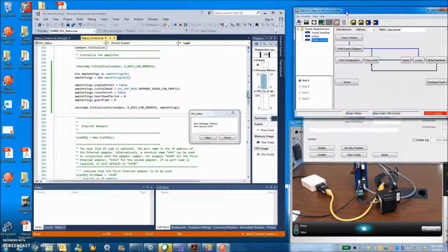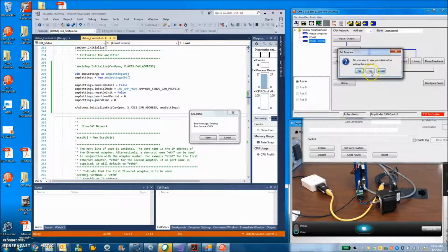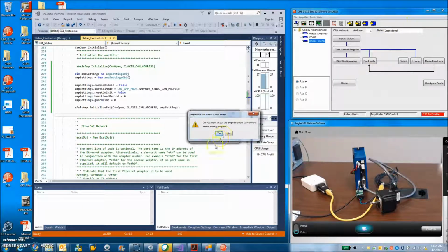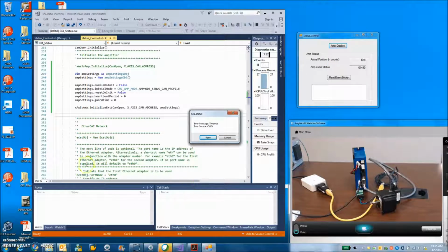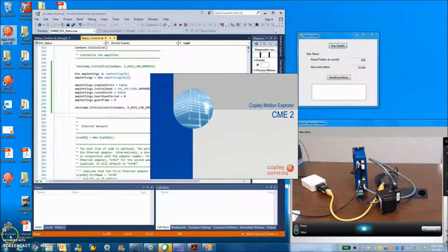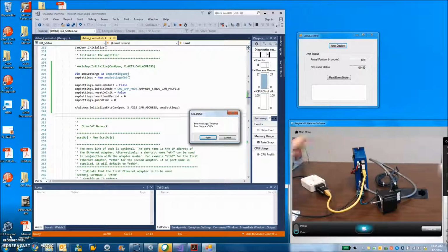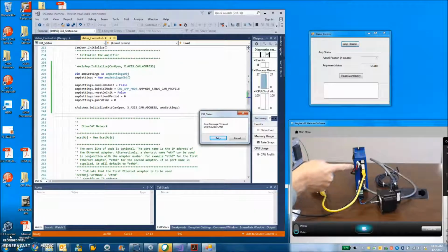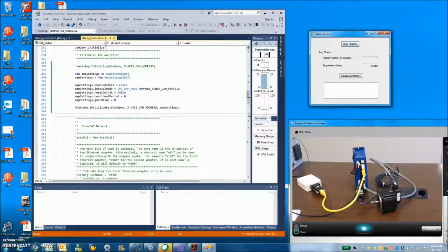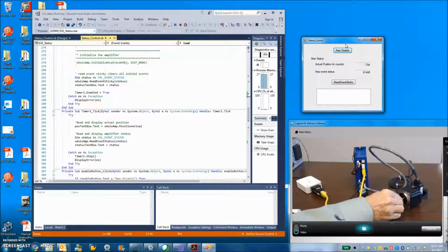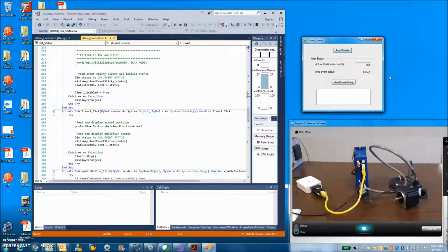So what I'll have to do is reconnect the CAN network. So let's hope that's under serial control here. So let's hook this back up. Status light's good for the CAN. Drive's disabled. Let's try retry on the timeout. There you go. Everything's good. I can enable and disable the drive. Turn the shaft of the motor. See some actual counts. And read the sticky events.